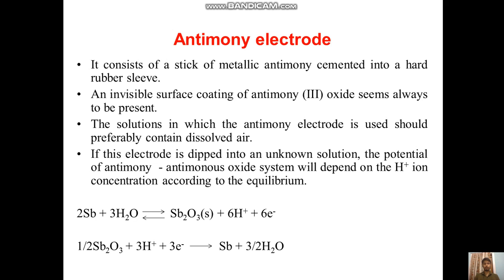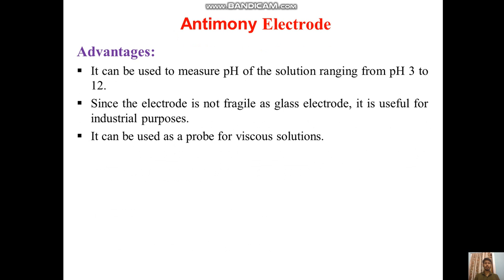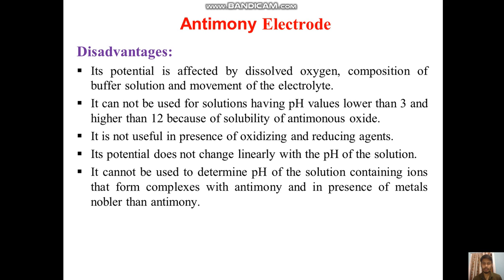The equilibrium reaction is shown here. The antimony electrode can be used to measure the pH of solutions ranging from 3 to 12. Since the electrode is not as fragile as a glass electrode, it is useful for industrial purposes, and it can be used as a probe for viscous solutions.